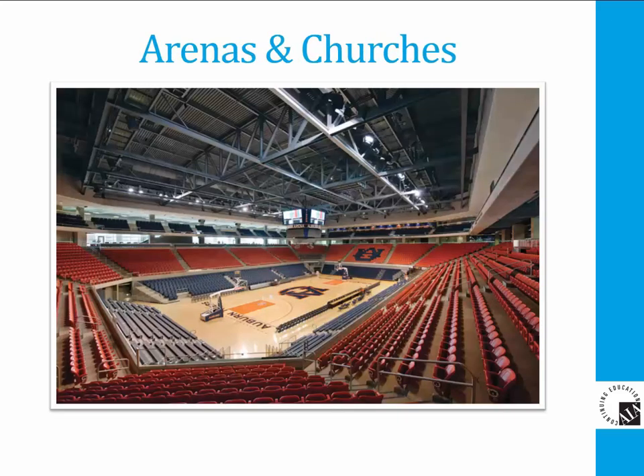Sporting arenas and large churches employ general air distribution from above the occupants. For stadium seating, supply outlets should discharge cool air horizontally and let the drop from buoyancy condition the occupants in the front lower seats. When architectural demands for hidden outlets are required, the rules of airflow discussed earlier will still apply.